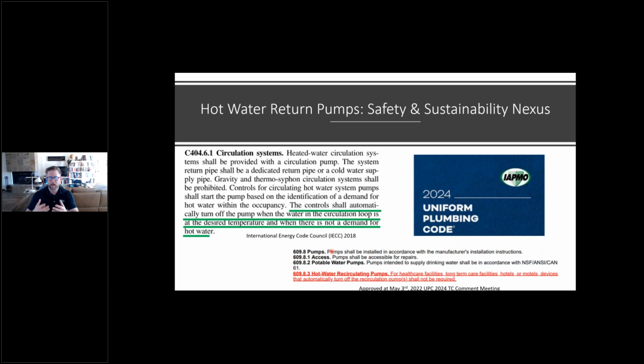So let's say you had an aquastat on a hospital and your hot water loop was running and you shut it off. Your whole loop is not circulating or recirculating anymore, I'm sure I'm using the right terminology here, and part of that will cool off. That section that's not flowing will cool off. Then let's say you turn the pump back on when the sensor back at the pump calls for it. That water is going to start flowing again, and your closest loops are going to start seeing that temperature increase. Now, depending on what's happening with your system and where flow is going, that coldest loop, that furthest, most hydraulically remote loop, may not ever get back up to that temperature to be in that design temperature range.